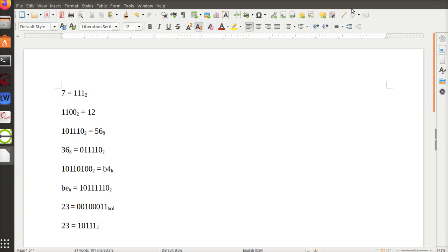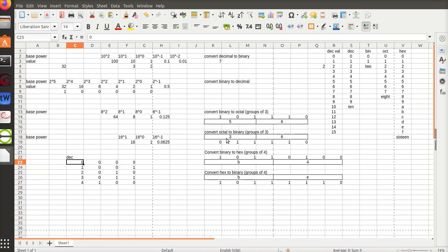And the reason we do it is because in PLC, your addressing is often in octal or hex. And that has to do with the number of inputs on an input card. For some PLCs, you have 0 through 7, so they're just octal. Some of them are done hex, some of them are like twice the octal. So you can have data in your PLC in an octal or a hex form. And it just has to go with the bits that are actually coming in on an input card. And that's why it's important. And I think there's a question on that at some point.